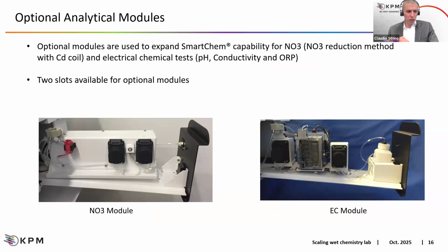When speaking about consolidation, one big plus is that we can also keep our discrete analyzers with add-on modules, where we can see here on the left the add-on module to run NO3 testing, so NOx, TON testing as per cadmium reduction. Of course, on all our discrete analyzers, TON, NOx can also be determined via hydrazine reduction and via vanadium chloride. And moreover, we can also optimize and automatize electrochemical testing on the same platform, because we also have an add-on module where we can determine pH, conductivity, and ORP.